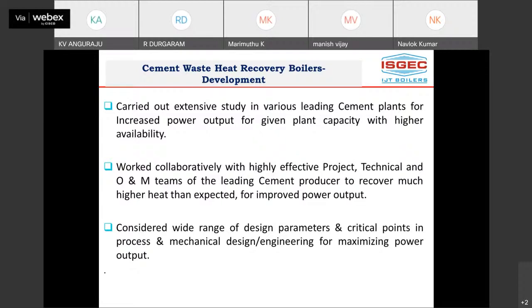Then we studied what the customer wants, like what Manish was referring to about the damper material selection, as well as the higher gas outlet temperature and how to really control it. Then the air ingress issue, and slagging and fouling: how the hammering arrangement is to be made, how the impact is studied, and what sequence we need to provide. All these are well understood by our design team, and accordingly they are taken care of in the design.